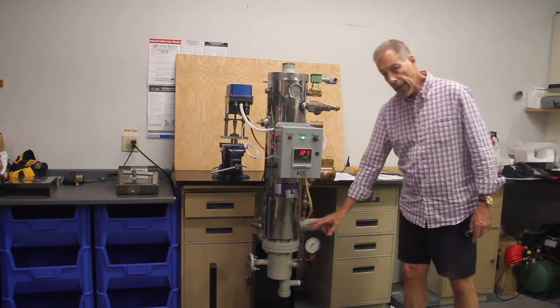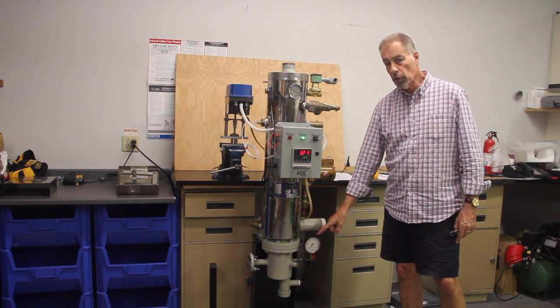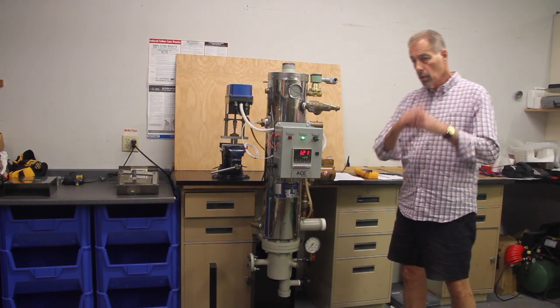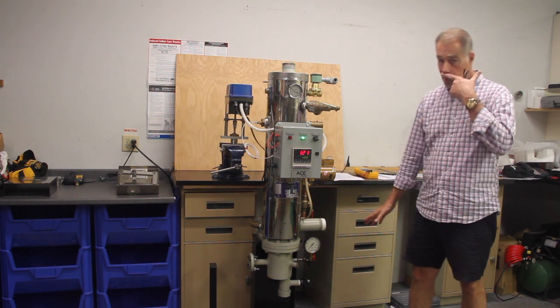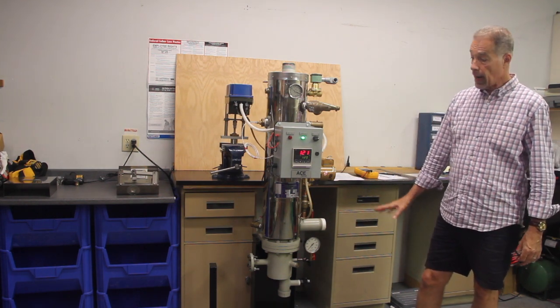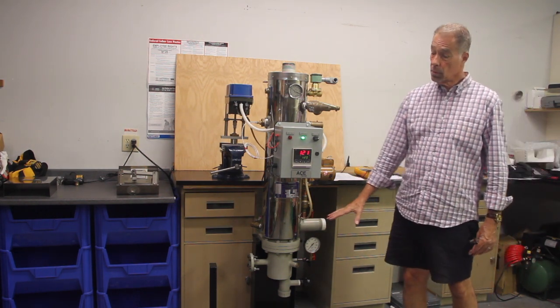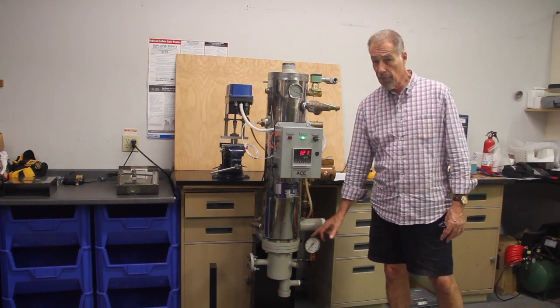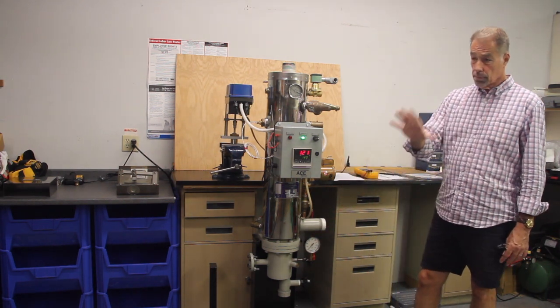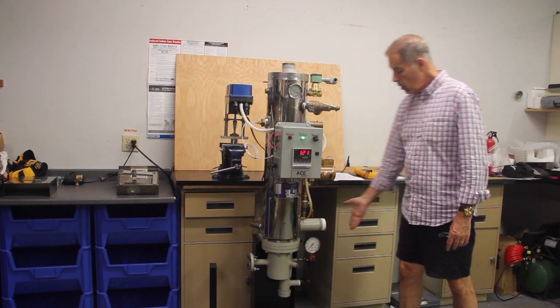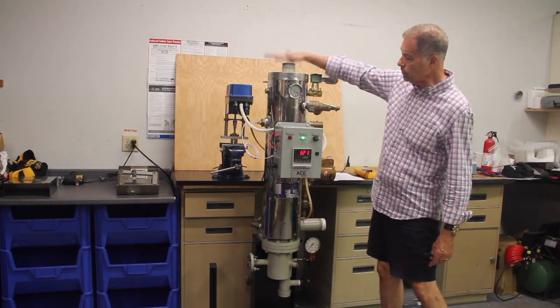The purpose of that gauge is if you see pressure on that gauge, sustained pressure, that means you've got back pressure in your condensate line, and that's bad news for this heater. So we put that pressure gauge there for maintenance purposes. Cold water in, as I said, hot water out.